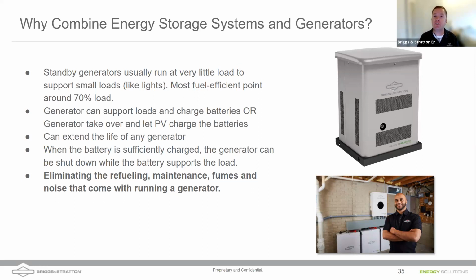So what you're doing is you're not really running that generator at the most fuel-efficient point. Really, we want to be up more like 70 or 80%. We don't want to be pedal-to-the-metal running at 100%, but let's get the generator working hard for us and run it hard for a short amount of time rather than coasting it for 10, 12 hours, however long the outage may be.